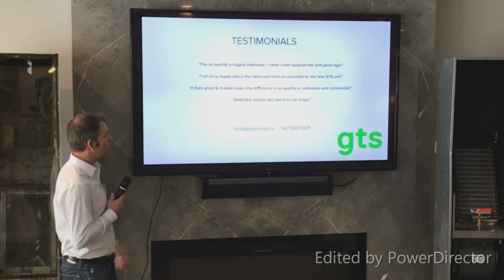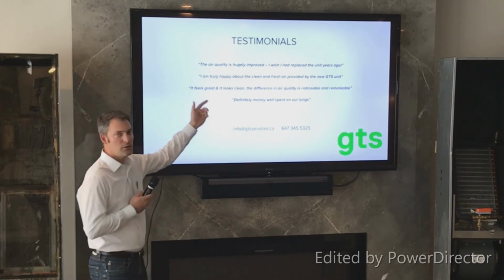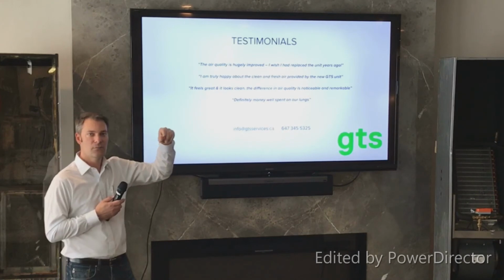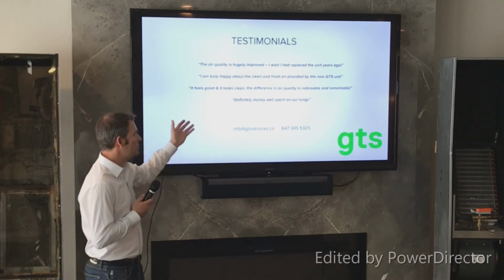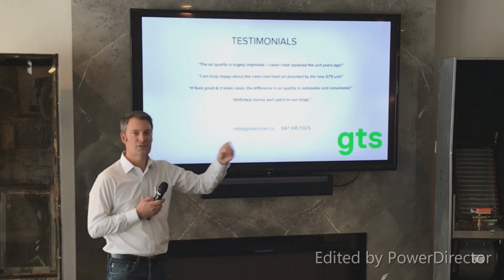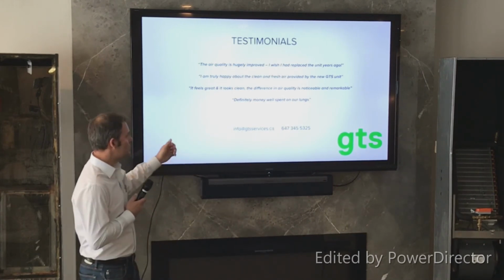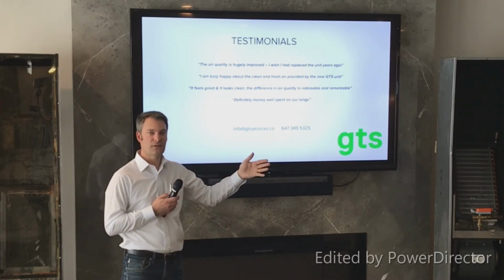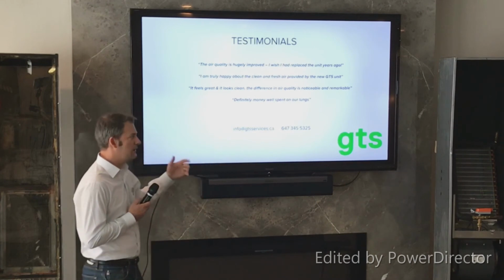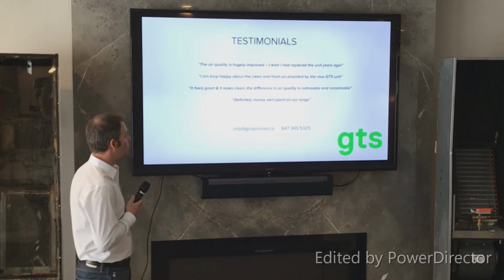And then we have some testimonials from some previous customers. So one of the big ones is air quality. So people complaining about, right now they get a lot of dust accumulating in their home. They've found with the new fan coil unit and because of the new insulation, the dust has dramatically dropped, which is, again, a big thing with fan coil units that are approaching 30 or are 30 years old. The original liner does fall apart and does cause dust accumulation in the home.